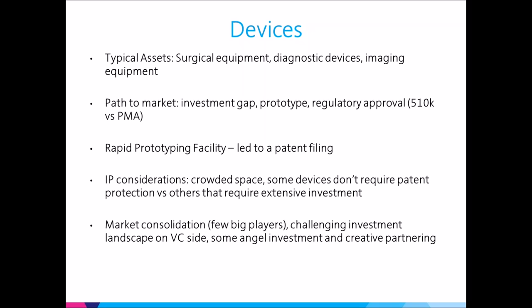In fact, it's threefold. It can be a class one device, which you just have to register - something like a glove or a gown, very simple and can't cause patient harm. Or a class two device, subject to 510K clearance, usually an iterative improvement on an existing device where you need to show substantial equivalence to a predicate device out there. Then the highest bar is a class three device, subject to pre-market authorization, which requires clinical trials, extensive development and testing, and funding to push forward.